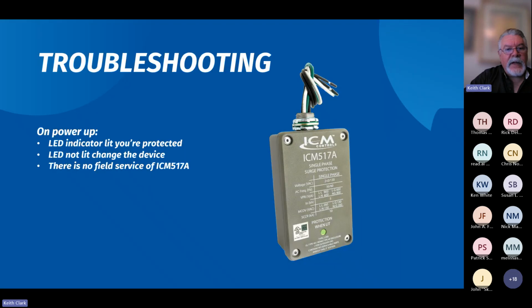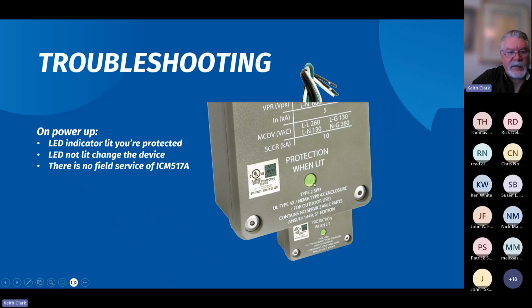So let's see what we got here. Troubleshooting, nothing to it. Basically, it's got an LED indicator down here at the bottom. If the LED is lit, glowing green, you're protected. If it's not lit, it's time to change the device. So you're not going to fix anything internally inside this device. You're going to take it out and wire a new one in. Simple as that. And based on some of the feedback that I've received from our engineering department, that is a very rare occasion.